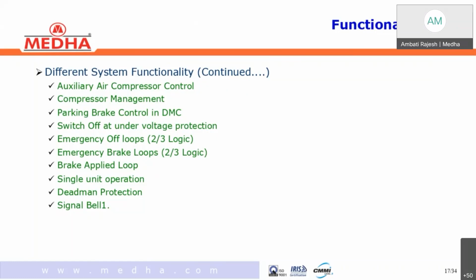2 out of 3 logic means there are 3 loops in emergency off loop, EOL or EBL. There are 3 loops, 2 hardware loops and 1 software loop. Total 3. Out of 3 loops, any 2 loops should be in okay condition. Then the system thinks that this is okay. Right? 2 out of 3 logic means out of 3 loops, 2 loops should say okay. And signal bell, we know very well, is for communication. So these are all the functions.